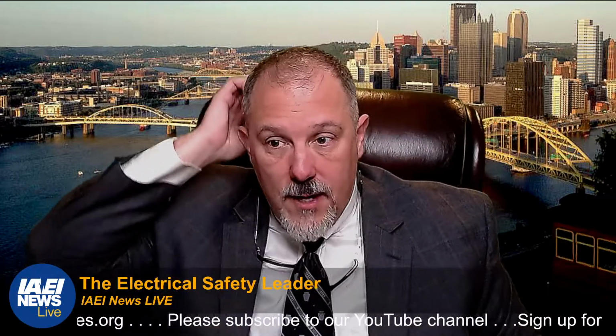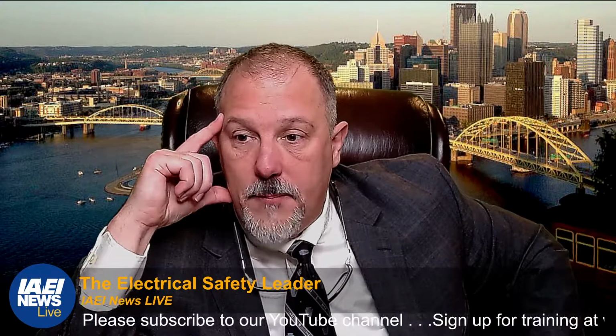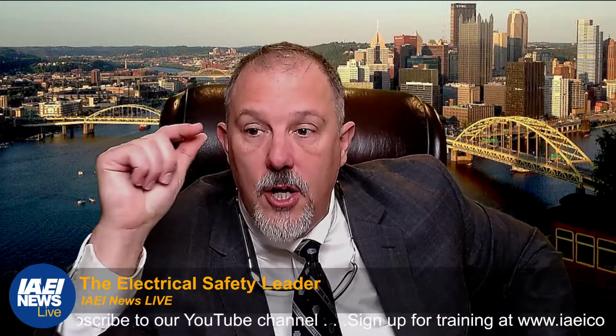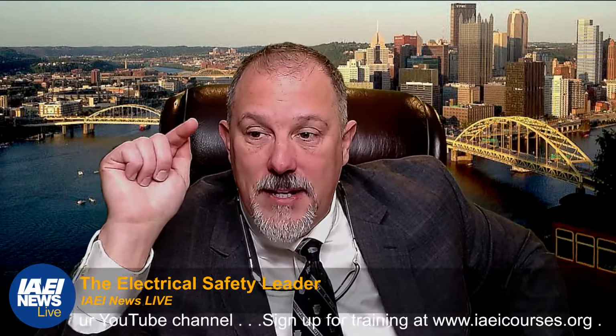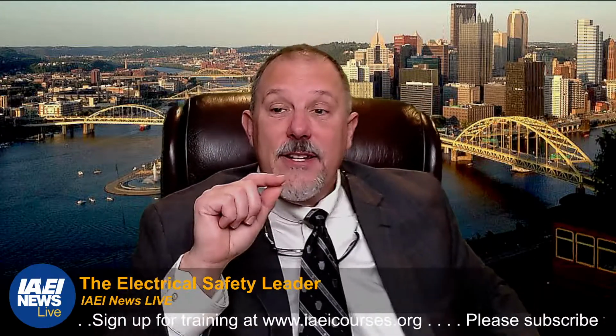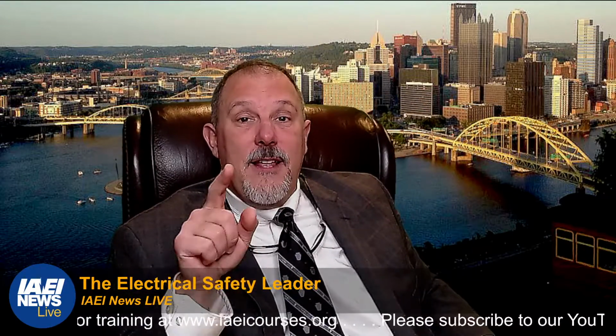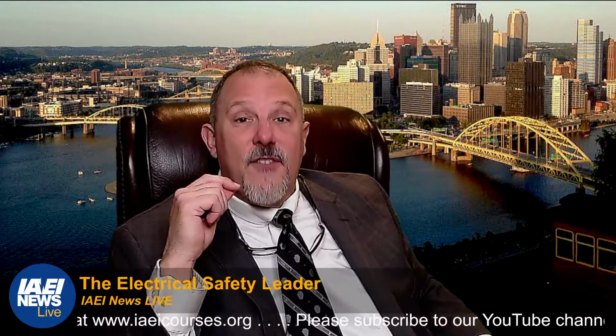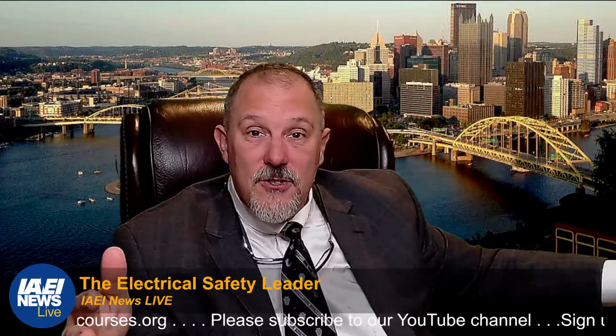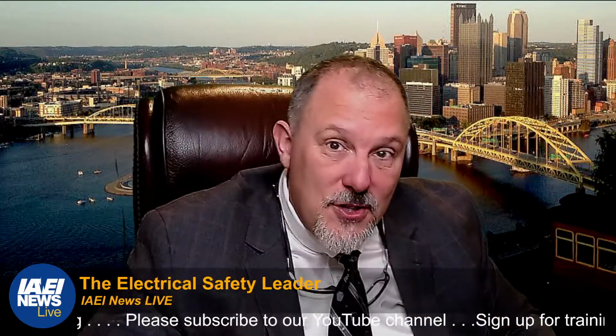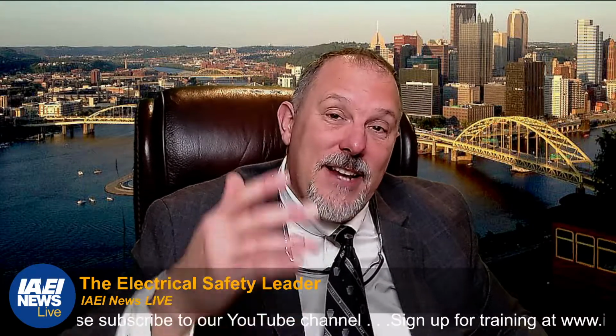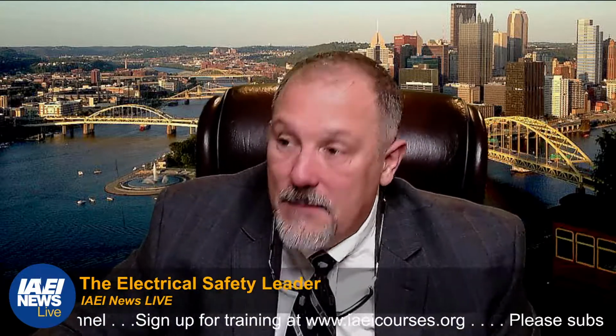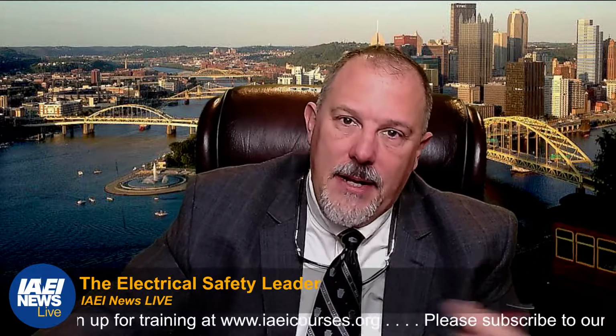So Robert from Omaha says the reason for 70B is the power, the energy when equipment was installed, has not changed in the time equipment has been in use. Equipment has worn down over time, but the power has not. That is true, Robert. And I could make an argument that the energy in that facility may have gone up. I added more motors -- even if I reduced the motor contribution, I could have longer clearing times. I could say I've changed the environment. So it's important for us to understand maintenance is important.